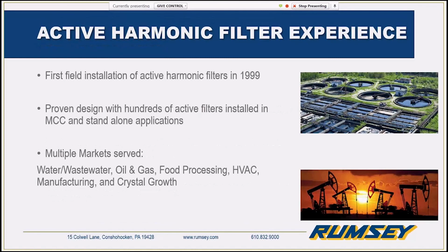Speaking back to that first active filter that we put out in the field, it was actually for an induction heating customer. They had 7 of our inverters, and they were using the voltage waveform as a reference for a significant amount of laboratory equipment, and our inverters were obviously distorting that waveform. So they said, "Oh, what can you do? What can you do for us?" And that's when we came with our design.